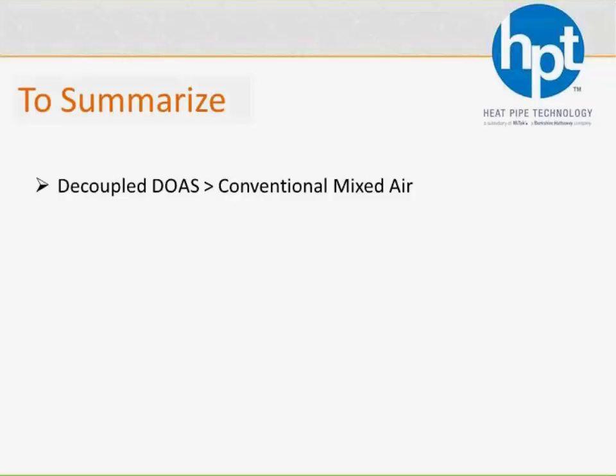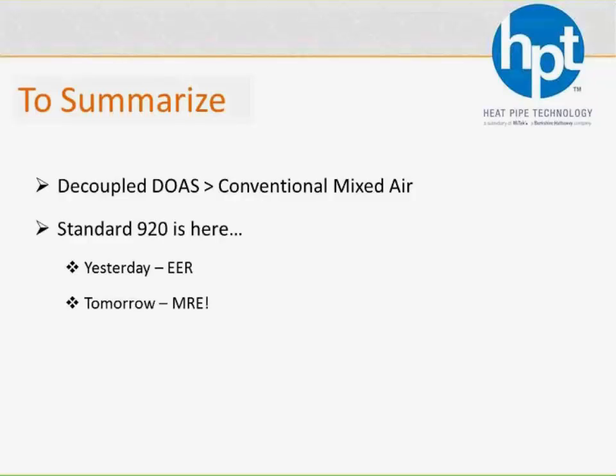Decoupling that outside air to let it solely focus on the ventilation air is a highly superior way of doing things. And Standard 920, again, it's new, it's here, EER is still around, but it's a thing of the past when it comes to DOAS. Don't be talking EER when it comes to your DOAS units. Talk about MRE. They're all going to be talking about it, publishing it, and there are going to be minimum requirements that I would not be surprised if a handful of the current DOAS equipment manufacturers out there are going to have to make some major improvements to hit these new 90.1 requirements.